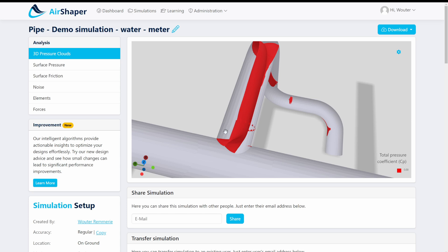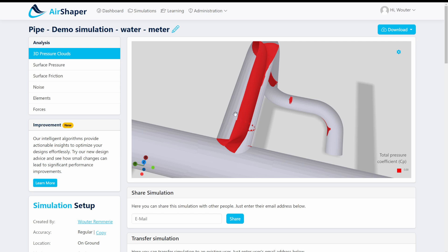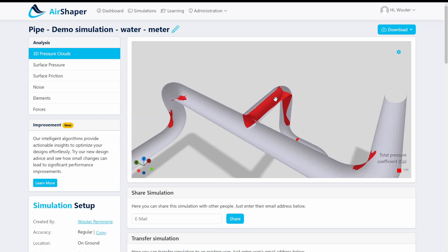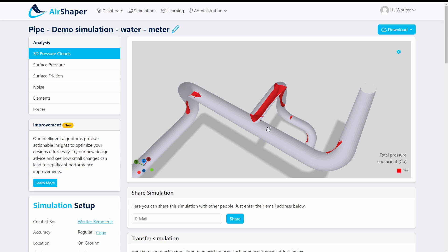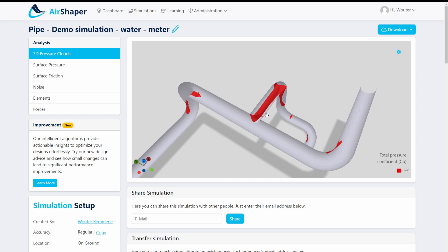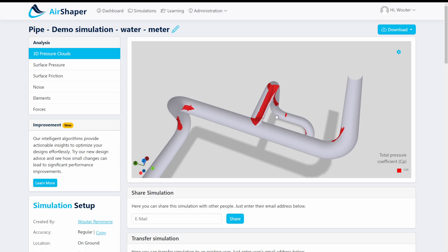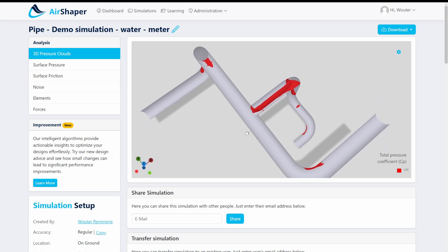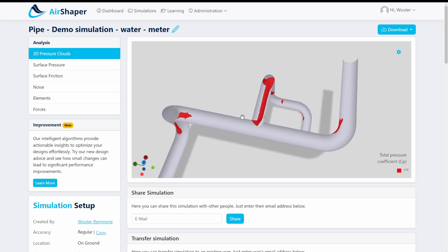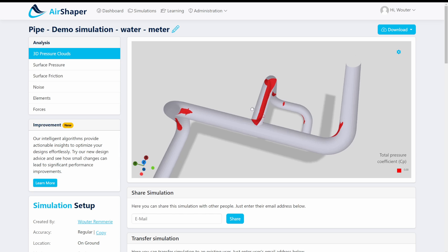And a bubble of energy loss and this represents a big pressure resistance for all of the water that wants to go this way which means as we'll see later on that you actually emphasize the flow going this way and this one is actually penalized. It will not get a lot of flow. So if you want equal flow distribution then this is definitely something you should replace with like a y-junction or something.